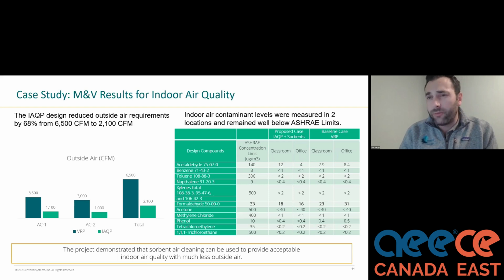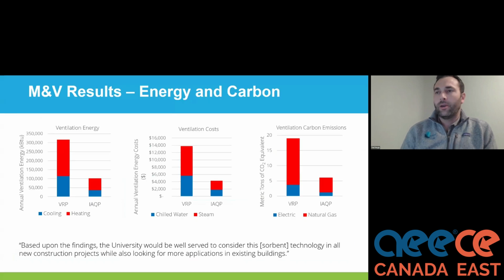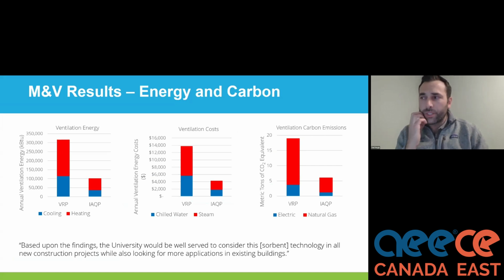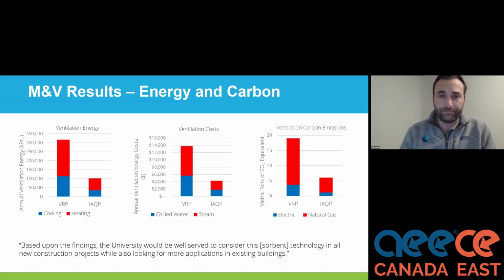So it's counterintuitive. By adding filtration, we actually improved indoor air quality. We think about that because dilution of contaminants is so far less efficient than extraction of contaminants. From an M&V perspective, from a cooling and heating standpoint, you can see the significant reduction in carbon emissions, ventilation costs, and ventilation energy as well. So just with 2 filter boxes, slicing the CO2 emissions from just shy of 20 tons of CO2 per year down to around 6 tons of CO2 per year, super helpful for any decarbonization goals.